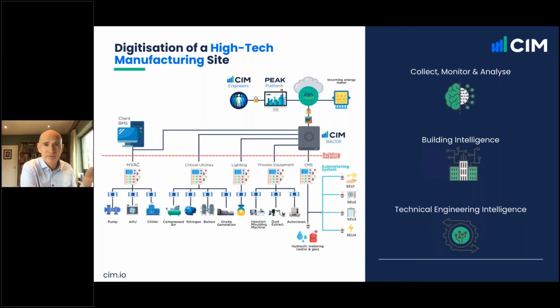Some sites we work with have their own on-site nitrogen generation, and some have on-site generation systems as well. And then there's bespoke process equipment. Now, just to be crystal clear, we don't play in that space. We don't optimize process equipment because it's very specific to each site we work on, but in some instances we can get data from it, and we can use it for the client's understanding, to see what's driving the consumption of critical plant and equipment. Chill water being an example, compressed air being an example. It's marrying that consumption to what the process equipment is requiring.